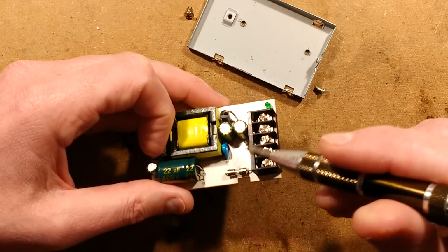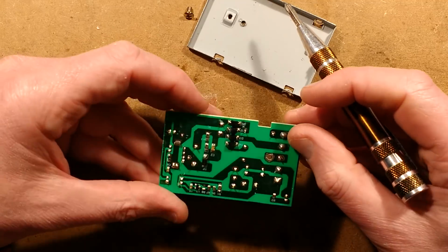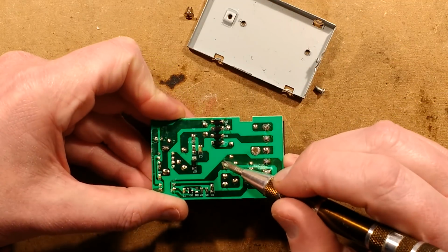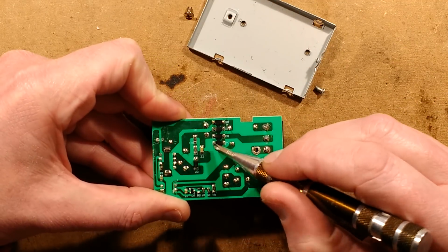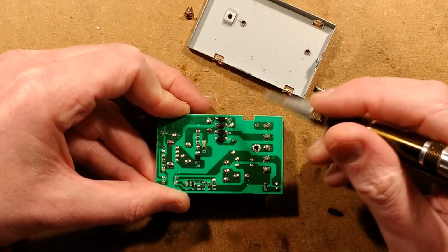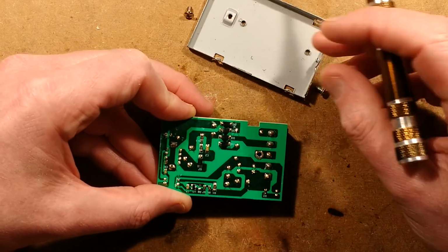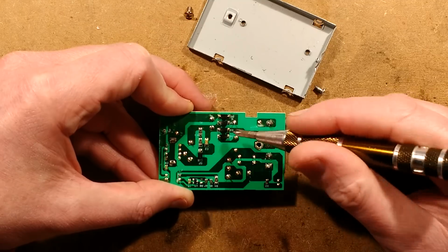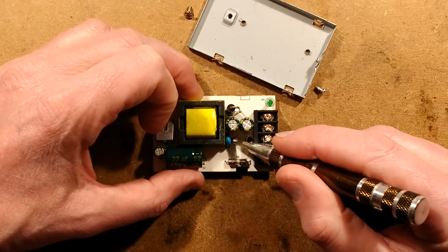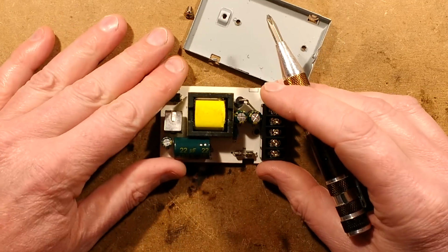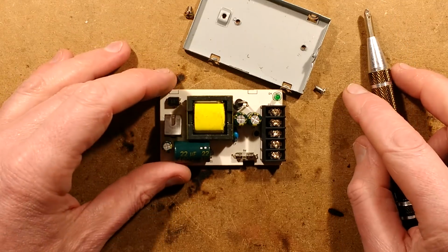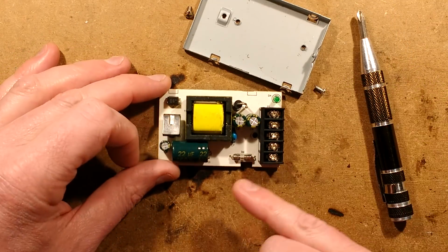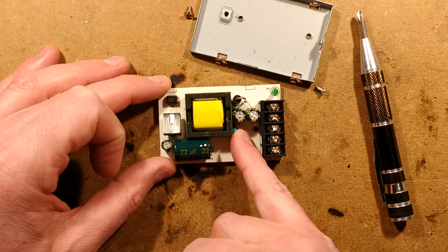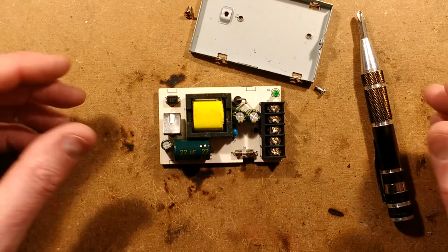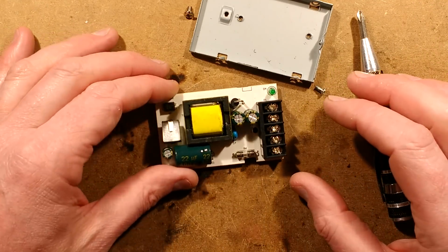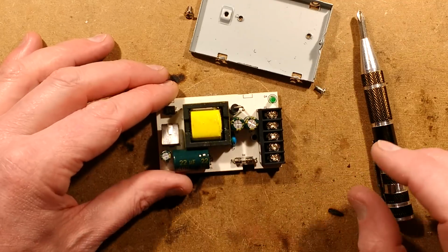Oh, there is a class Y capacitor, going from the bridge rectifier negative across to the negative - so it's negative to negative on both sides. Now, I did the high voltage test from the input to the output on this. I did right up to 2000 volts, and the only leakage must have been through that capacitor. I was only getting about 0.5 milliamp leakage in the AC test. That's actually fine, it has passed its input to output test.